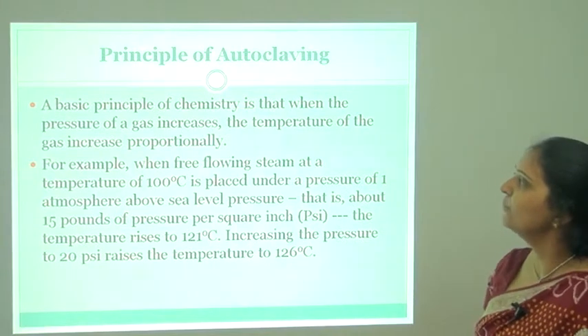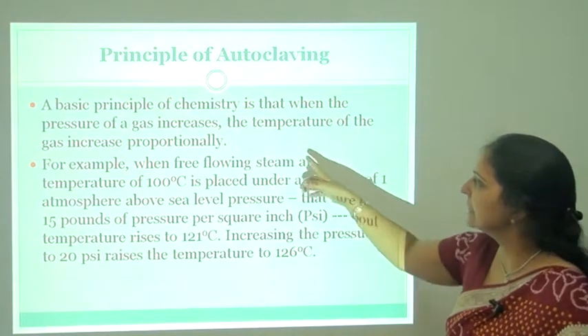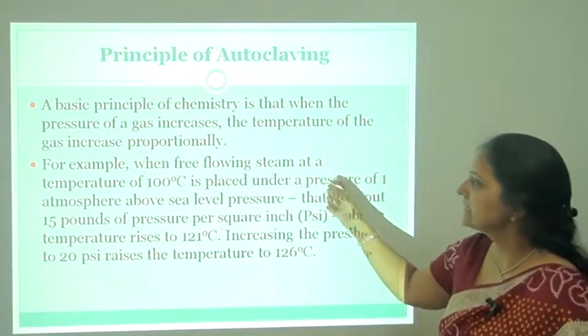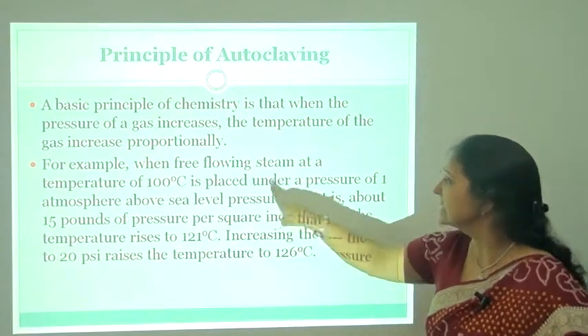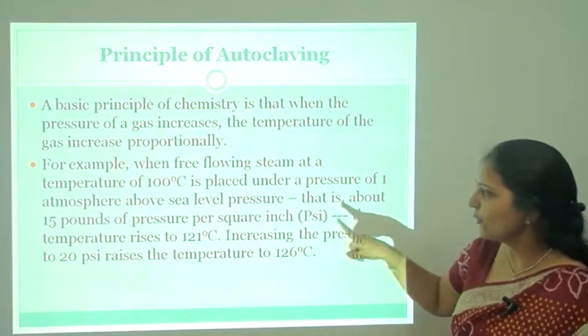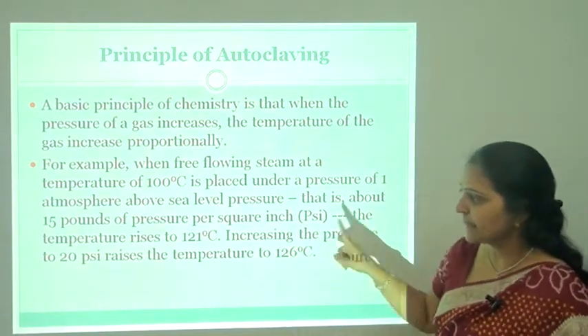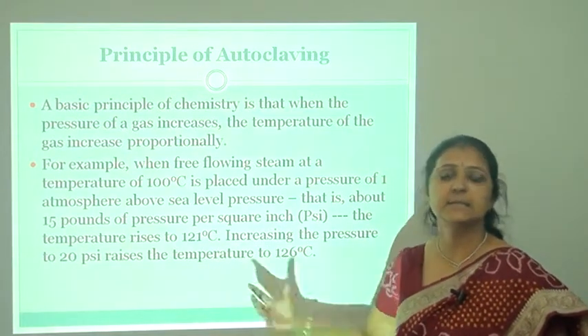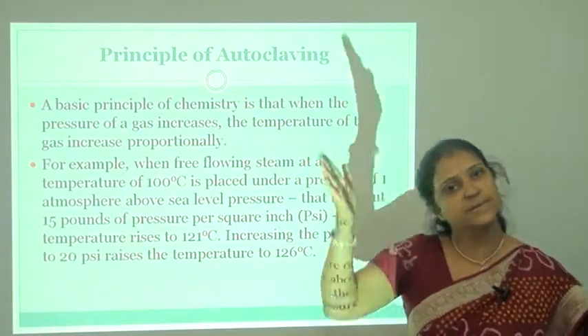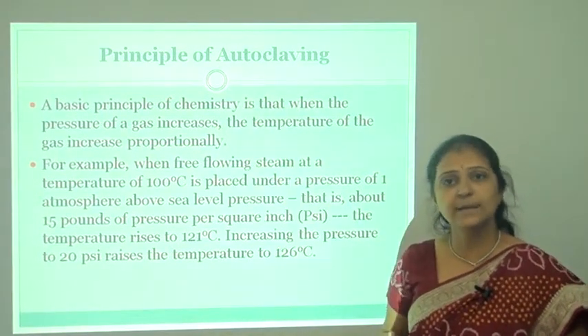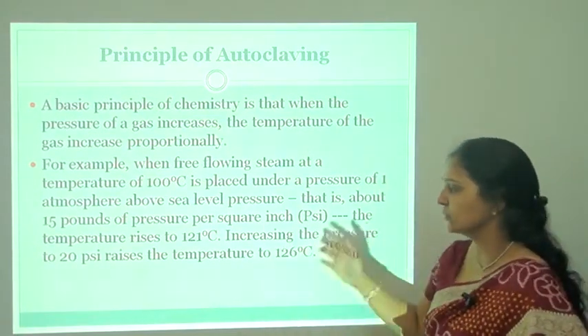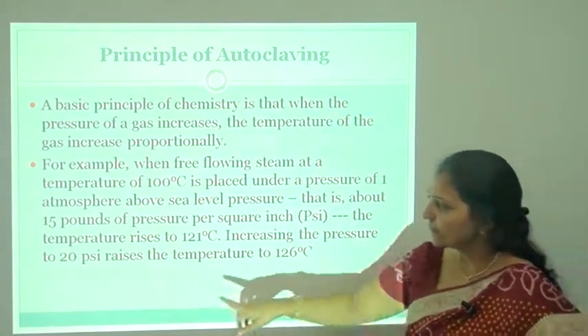The principle of the autoclave is that when the pressure of a gas increases, the temperature of the gas increases proportionally. For example, when free-flowing steam at 100°C is placed under a pressure of 1 atmosphere above sea level pressure — about 15 pounds per square inch — the temperature rises to 121°C. As pressure increases, temperature increases simultaneously — both are proportional and together they reduce the growth of microorganisms.